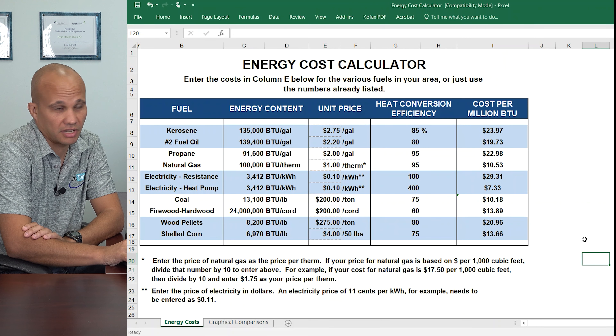So what I want you to focus on is the two electric options: electric resistance and electric heat pump. Both of them cost me 15 cents a kilowatt hour. The other spreadsheet was great for comparing one heat pump to the other. But if somebody is on all electric — electric resistance heat — and they do not have a heat pump today, you have to get them on a heat pump. Because electric resistance is 100% efficient — it's perfect — but a heat pump is 400% efficient because the heat pump doesn't make any heat. Natural gas, propane, electric resistance — almost everything on this list — takes a fuel and converts it into heat. But a heat pump doesn't do that. A heat pump uses electricity to move heat from outside to inside. So I don't have to pay to make the heat; I only have to pay to move the heat. Therefore, it's significantly more efficient than 100% — it's the only thing on this chart that's more than 100%.